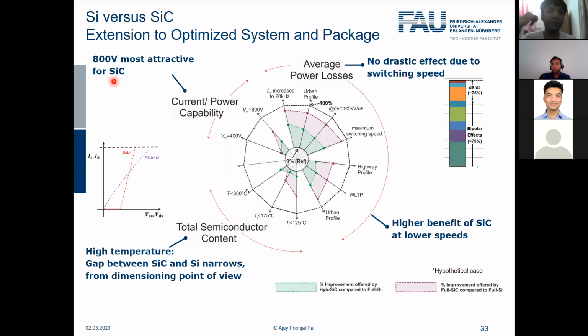Why is this? Because IGBTs are not so optimum at this voltage class. For an 800 volt system, you would need a 1200 volt IGBT, and in this voltage class IGBTs are not so attractive because they are bipolar devices. The breakdown voltage has a direct impact on the drift region, meaning that a 1200 volt IGBT would need a thicker drift region compared to a 650 or 750 volt IGBT.